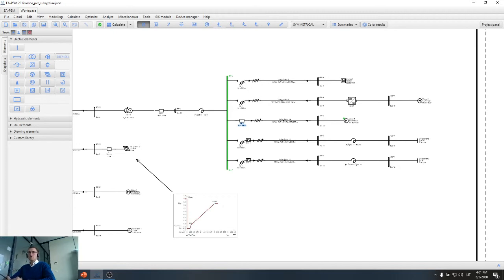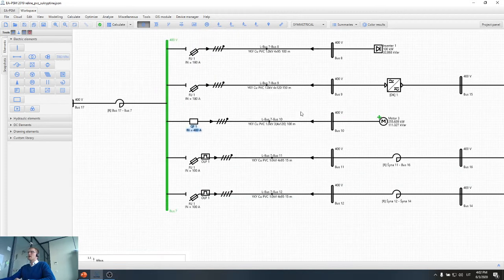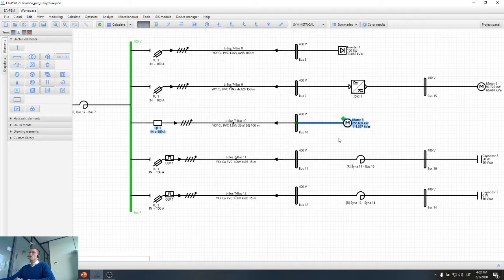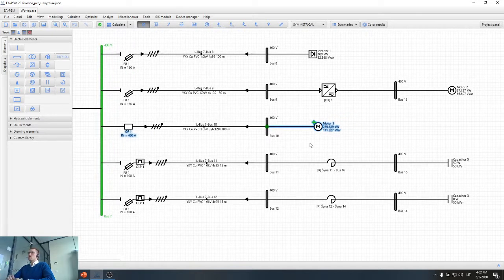However, asymmetrical short circuits like one phase, two phase with ground, are more frequent. A three-phase short circuit is not that frequent. It happens from time to time, but it's quite rare, while a one-phase short circuit will happen quite often in electrical networks. And this kind of asymmetrical short circuit also overheats the equipment. Also, like I mentioned, it's very damaging to motors that cannot work with only several phases operating, and inverters cannot operate, so it's hard to say which damages the equipment more. Actually, both of them cause problems. However, a symmetrical short circuit usually provides most of the problems, because it provides the biggest short circuit current.